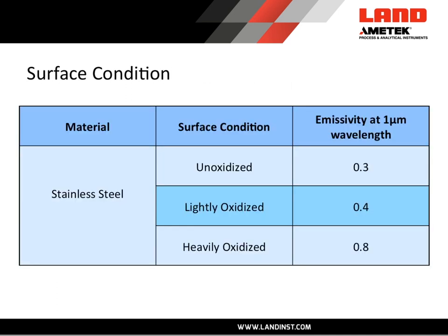Let's look at surface condition for one material — stainless steel. With an unoxidized surface, very smooth and shiny, the emissivity is 0.3, meaning only 30% of the energy is able to be emitted from the surface. If it becomes lightly oxidized, the emissivity goes up slightly. And if it's heavily oxidized, it goes up considerably.